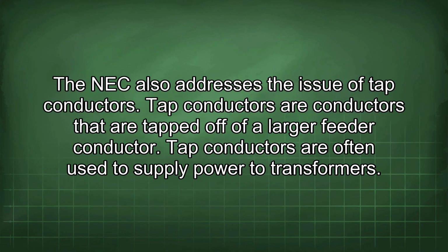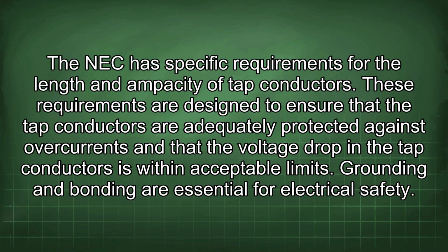The NEC also addresses the issue of tap conductors. Tap conductors are conductors that are tapped off of a larger feeder conductor. Tap conductors are often used to supply power to transformers. The NEC has specific requirements for the length and ampacity of tap conductors. These requirements are designed to ensure that the tap conductors are adequately protected against overcurrents and that the voltage drop in the tap conductors is within acceptable limits.